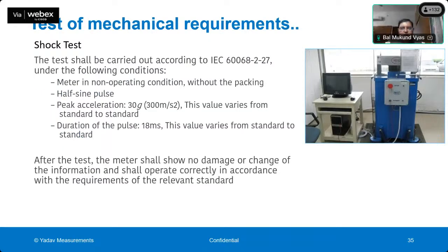So these are the tests for ingress protection of the water. Another important test for mechanical requirement is that the meter is subjected to shock. So you can see there is a shock testing machine shown here. The meter is mounted on this platform of the machine, and the machine actually subjects the meter to the specified shock.